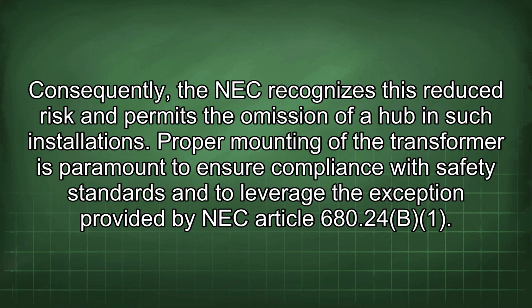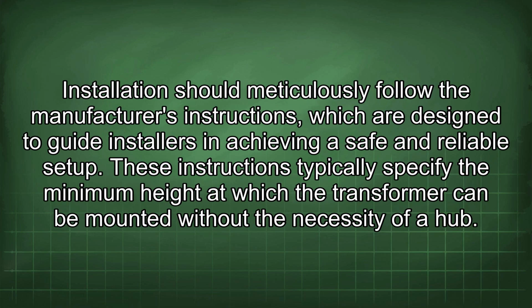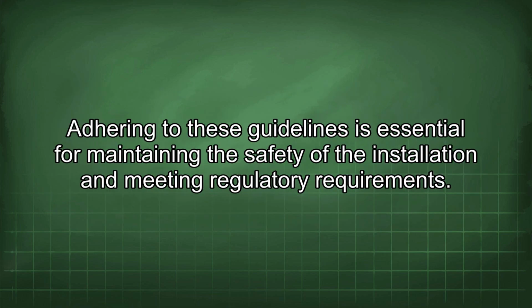Proper mounting of the transformer is paramount to ensure compliance with safety standards and to leverage the exception provided by NEC Article 680.24(B)(1). Installation should meticulously follow the manufacturer's instructions, which are designed to guide installers in achieving a safe and reliable setup. These instructions typically specify the minimum height at which the transformer can be mounted without the necessity of a hub. Adhering to these guidelines is essential for maintaining the safety of the installation and meeting regulatory requirements.